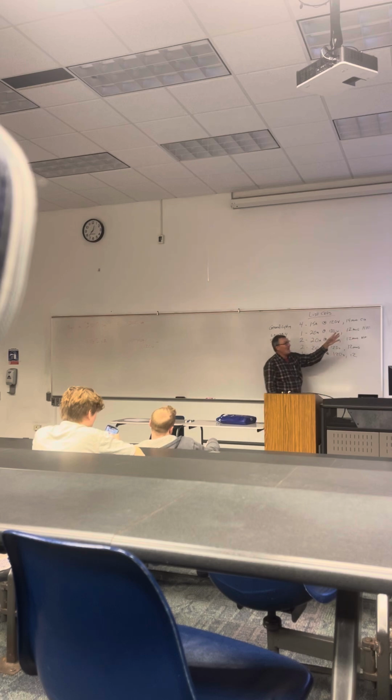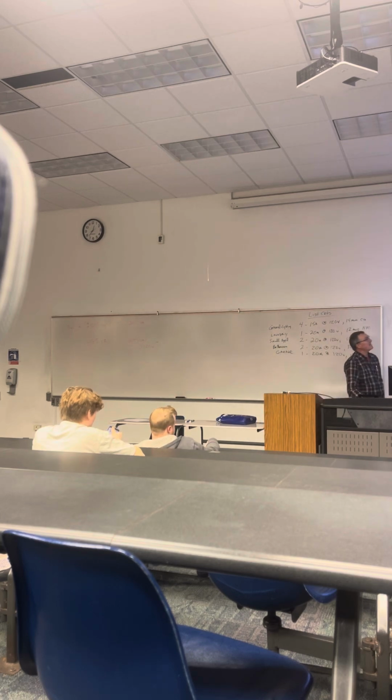Now, before I move on, this says for your attached appliances, if you have 3 or less, which we have more than 3, right? 3 or less is just the total of the VA. If it's more, it's only 75% of the total, okay? And it'll calculate it in there, right?